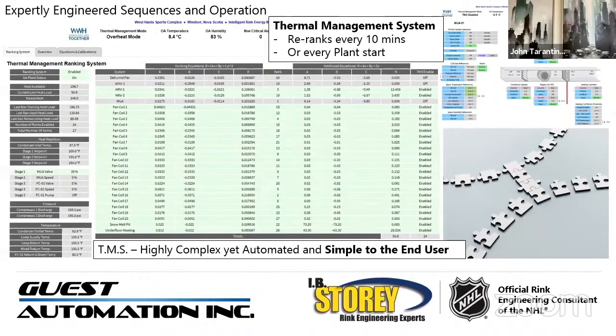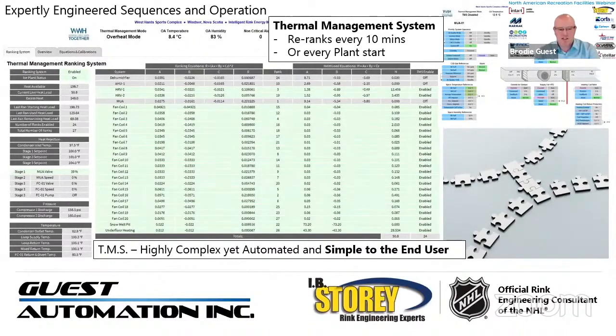work. In the main thermal management screenshot we have here, we see in the top left, the TMS, the thermal management ranking system, is enabled, it's green. And in this screenshot for context, showing when we had full ice plant heat available, we see the ice plant status is on, we see the amount of heat available, we see the live heat load, excess heat, etc. Continuing down the list, we see here, stage 1 of heat rejection is the makeup air heating valve. So essentially the building is almost satisfied. We are rejecting heat to heat the turf field. We're not throwing the heat outside, very efficient.